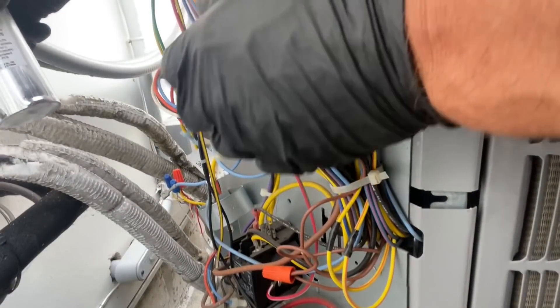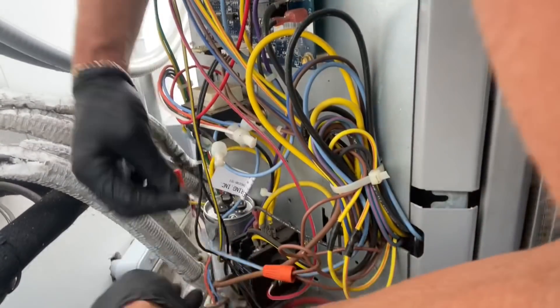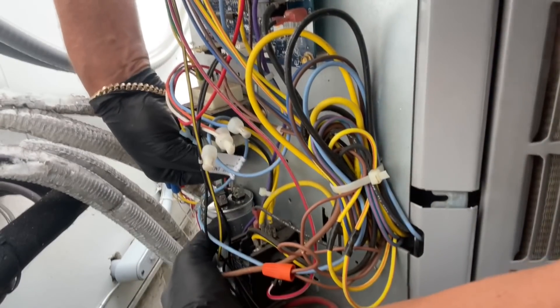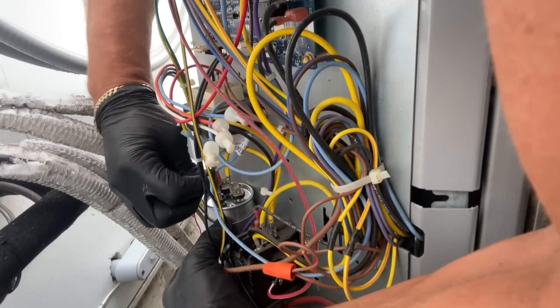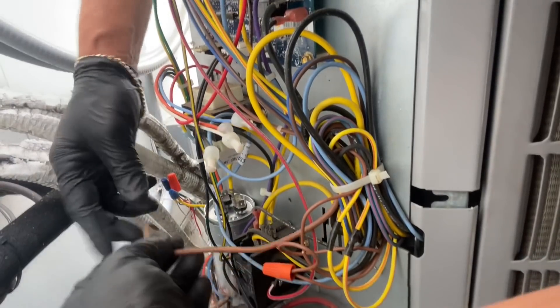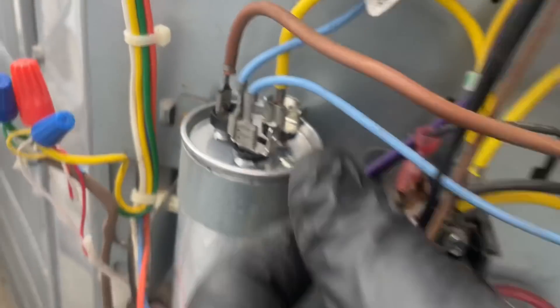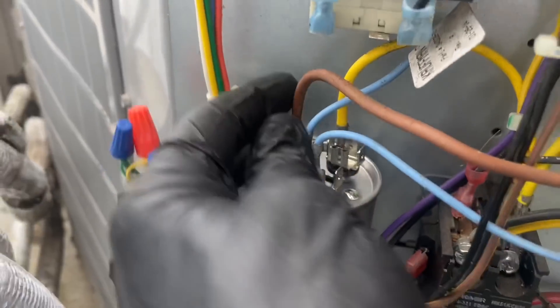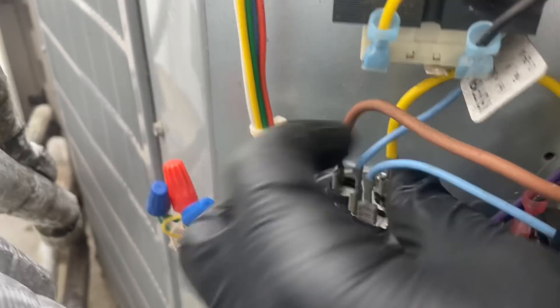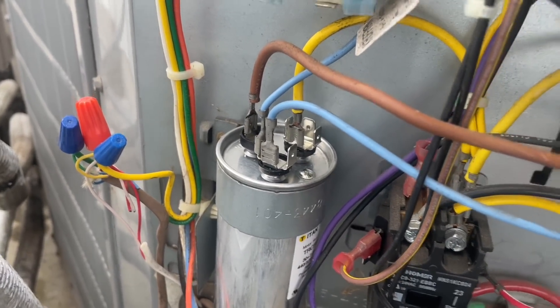I'm going to put my new capacitor in there — slides right in there. My yellow was common, the two blues were herm, and the brown was fan. I'm going to get a quarter-inch driver and tighten that up. So I've got my 30/7.5 dual capacitor secured, all wiring terminals are secure. We're going to see what happens — hopefully it was that simple.